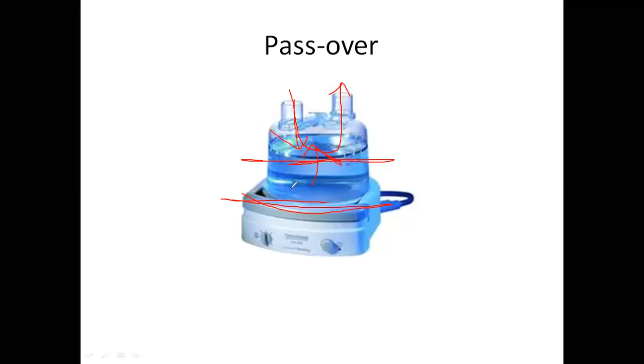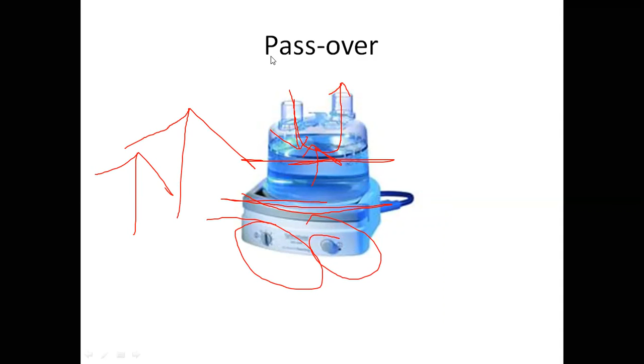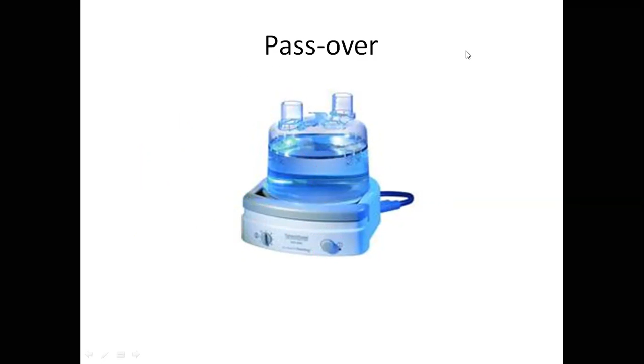Like I say, this is a passover humidifier. It's not as efficient and doesn't approach the humidities that the other style of humidifier uses, which is a wick humidifier. But nonetheless, it does a pretty good job. It has good technology. This particular one has just an on-off switch, and then you can adjust your level of temperature. And remember, the higher the temperature, the higher the humidity. If you remember those initial slides, we're talking about relative humidity. The warmer the gas, the more humidity that gas can hold. I wish I could draw better, but I can't. Forgive me. Okay.